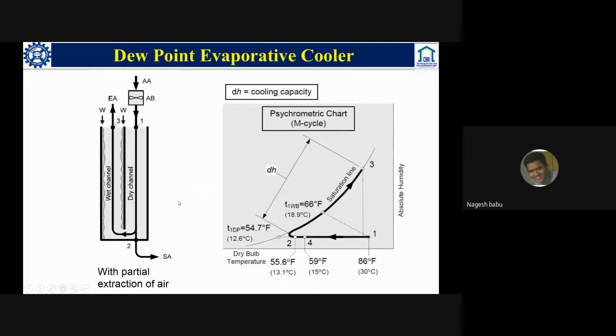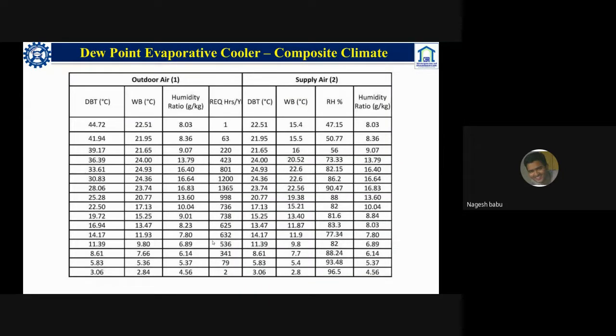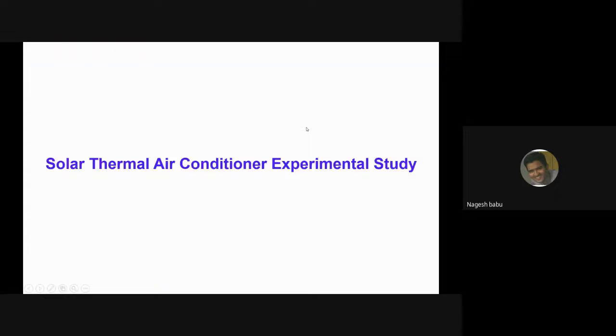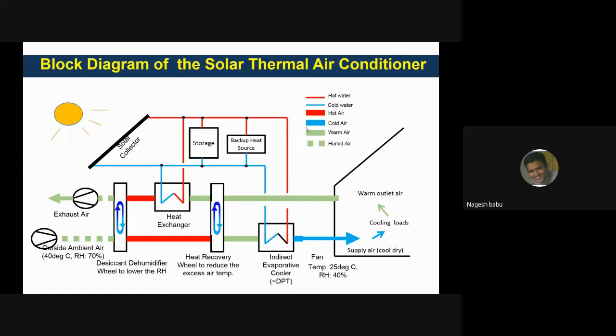So if you are supplying around 200 CFM, the delivery air will be only 50 CFM or 40 CFM. So we have to design for a higher fan, higher CFM ventilation. These are the results for a similar dew point cooler, in which, for example, at 45 degrees centigrade, we can reach a wet bulb temperature of up to 15.4 degrees centigrade. So that is a very huge reduction in temperature. Now moving on to solar thermal air conditioners.